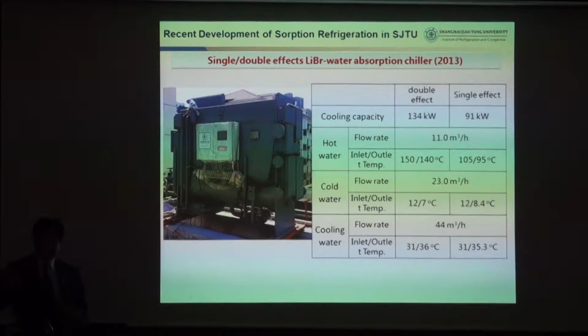And the other times, the temperature is lower. In this case, you use single effect. So you could develop this concept to use single effect or double effect, depending on the heating source temperatures. And then I think this kind of product might not be efficient, because for single effect you need a heating source of about 85 degrees centigrade, and for double effect about 140 degrees centigrade. But if it's in between, say 120 degrees centigrade, it could already operate in single effect, but the efficiency is very low. So in this case, we invented a new concept, the so-called one-point-N effect.